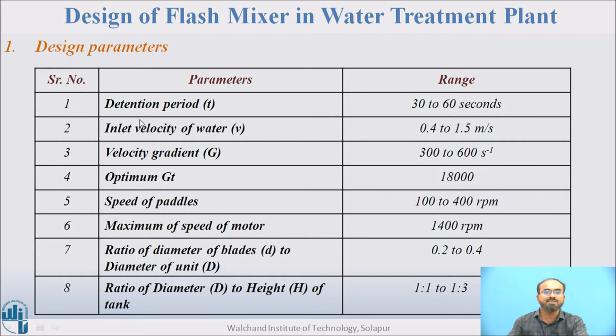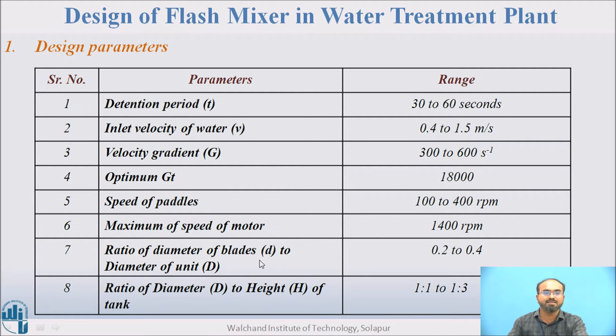For design parameters: the detention period is generally 30 to 60 seconds. Inlet velocity of water is typically kept between 0.4 to 1.5 meter per second. Velocity gradient, capital G, is generally kept between 300 to 600 per second. Optimum GT is always kept at 18,000. Speed of paddles varies from 100 to 400 RPM. Maximum speed of motor is generally kept at approximately 1400 RPM. The ratio of diameter of blades to diameter of the whole unit (small d to capital D) is kept between 0.2 to 0.4. The ratio of unit diameter to height of the tank (capital D to capital H) is kept between 1:1 to 1:3.